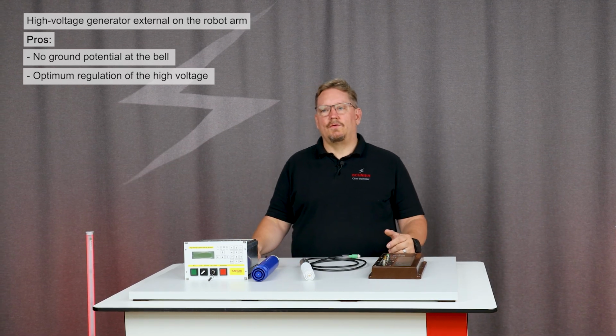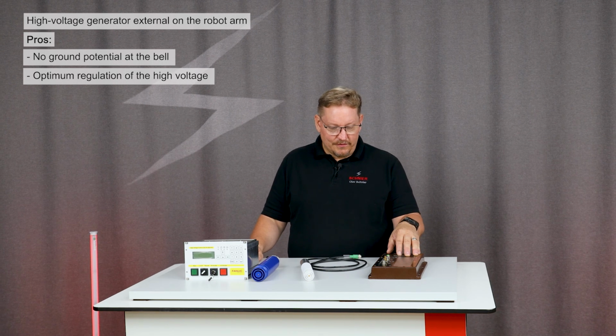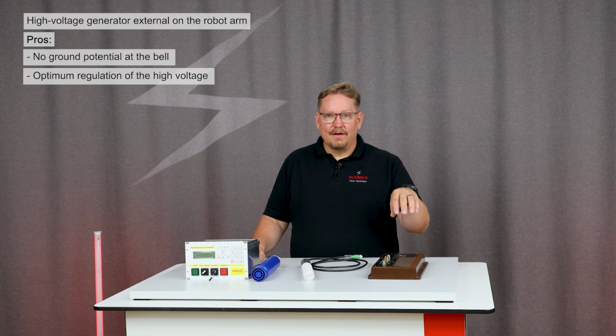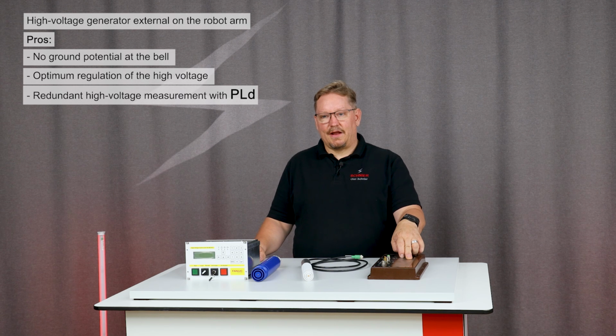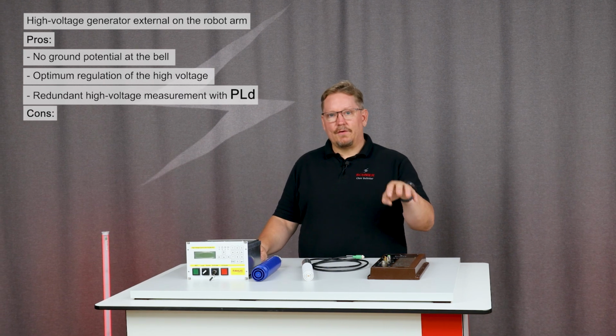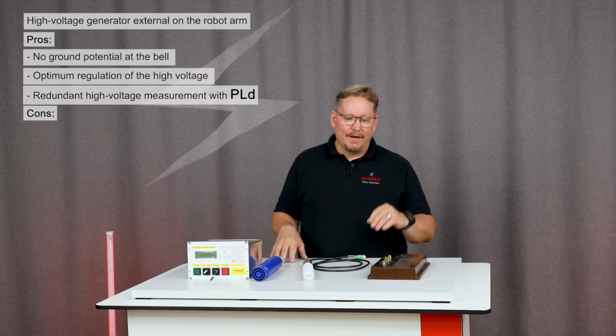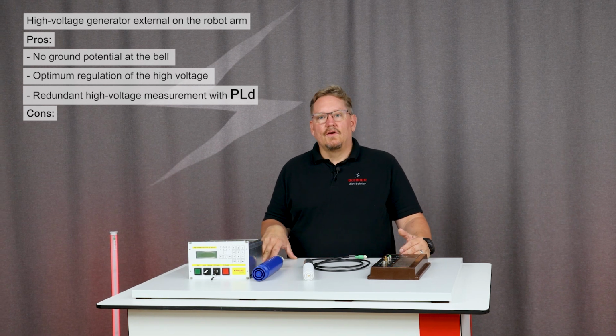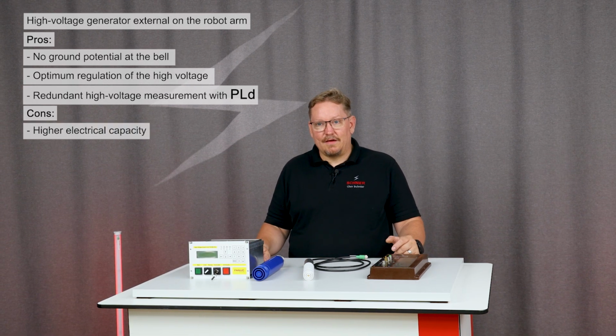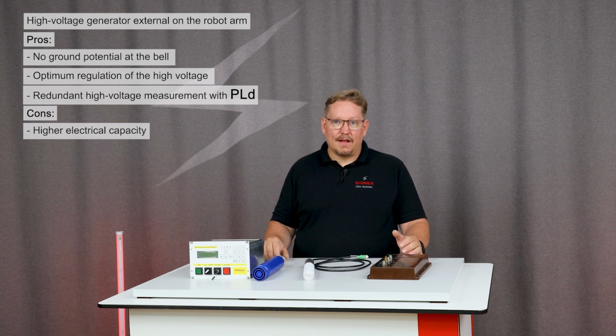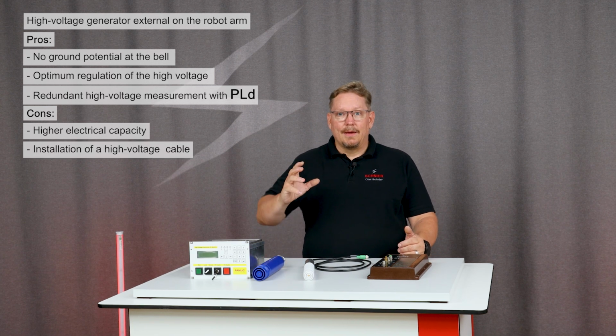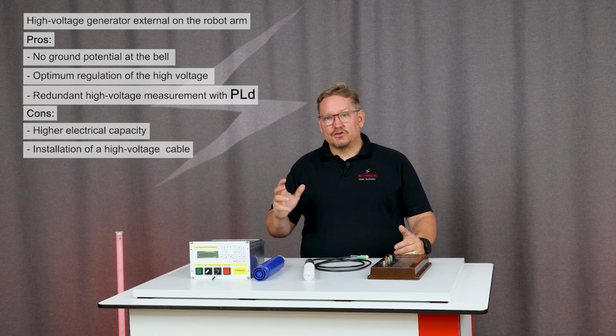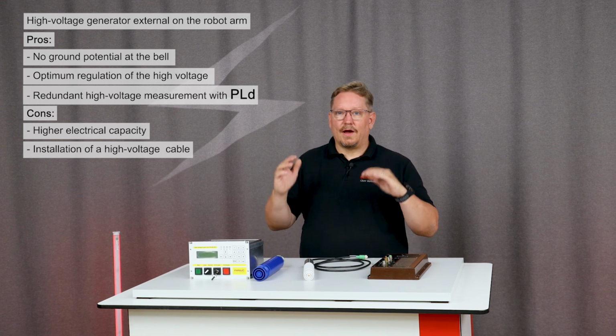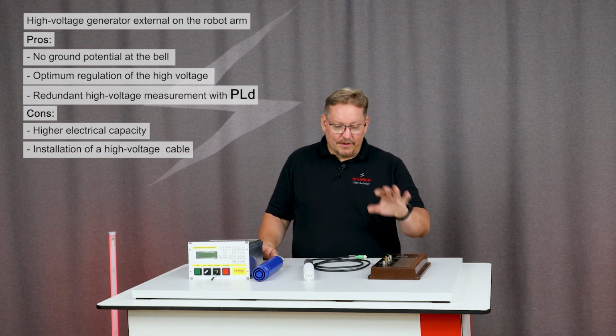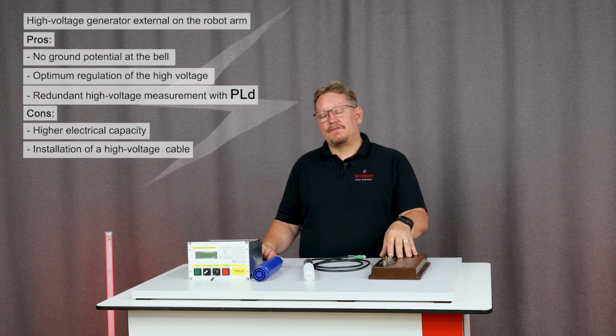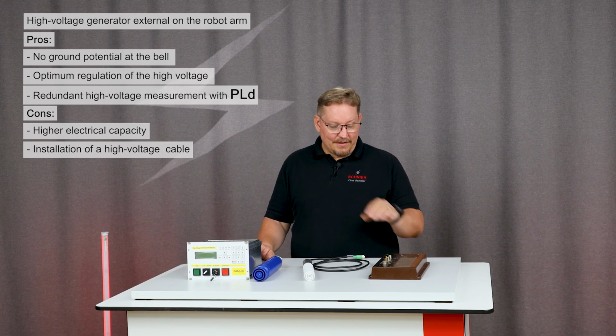A huge advantage, probably even the biggest advantage of a system like this one, is that we were able to realize redundant measuring resistors here. This means that the entire high voltage measurement is redundant, then goes to a safety relay, and we can report back here with a performance level. I am safely discharged. So safely discharged that I can even touch the atomizer with a flammable cleaning agent and clean it that is below the ignition limit, and with a performance level, which means that a door interlock can be implemented relatively easily.